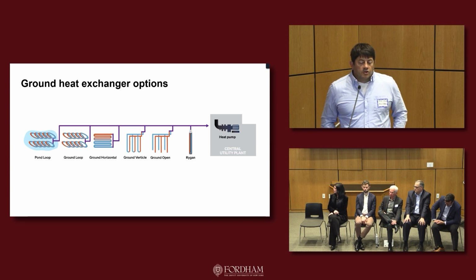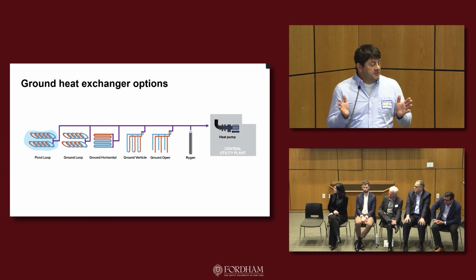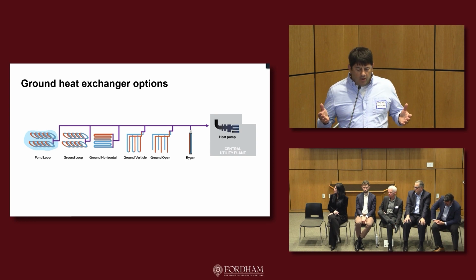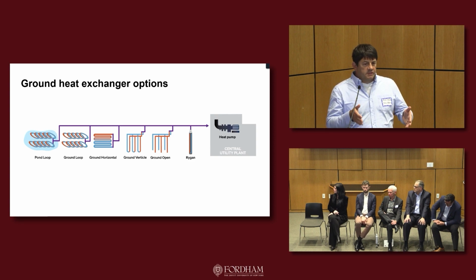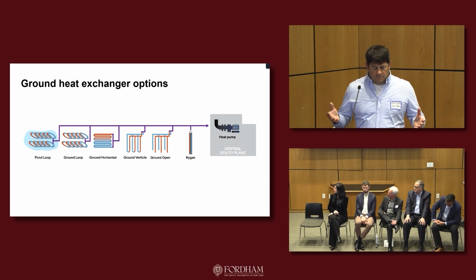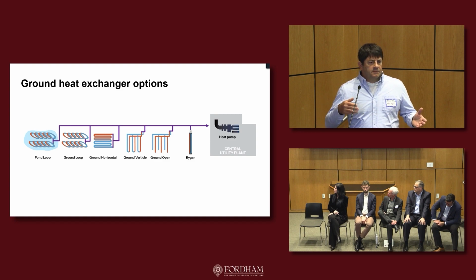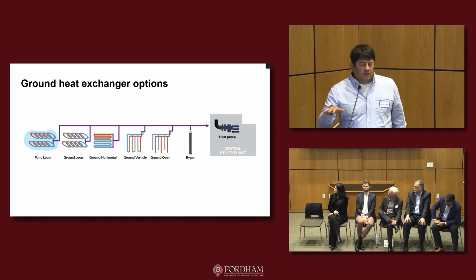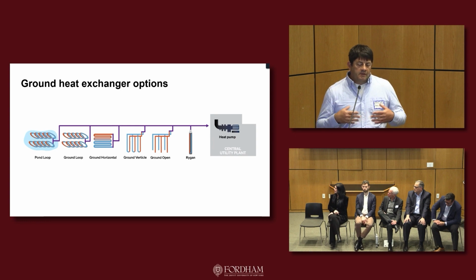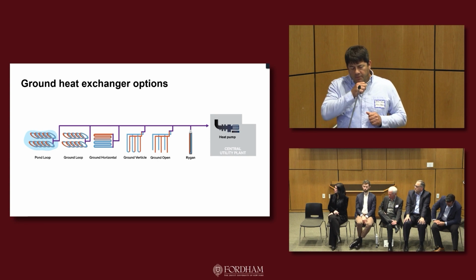When you look at your ground heat exchanger options, we have a lot of options today: open loops, closed loops, open bodies of water like rivers and lakes. You really have to understand what you have available at your site as an energy source. Do you have a retention pond? We use a lot of retention ponds as heat exchangers—they might be 4, 6, or 8 feet deep. We implement slinky coils underneath a sand layer with water on top. It's a very good heat rejection device, trying to get rid of cooling towers, whether it's heating dominant or cooling dominant.